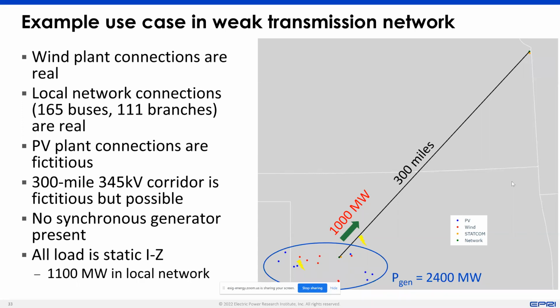Where I'm coming from is that the component would come with a grid forming technology that I want 100 megawatt of grid forming device at this location. It will not be that amount of application somewhere else, but the component says, okay, I'm coming with this, I'm going to install this. So that's where I'm coming from. That maybe you go with grid forming rather than grid following. So the benefit that it might provide at that location may not be the benefit that you want from the system. So that will play a role.